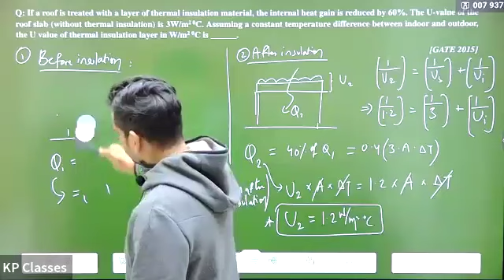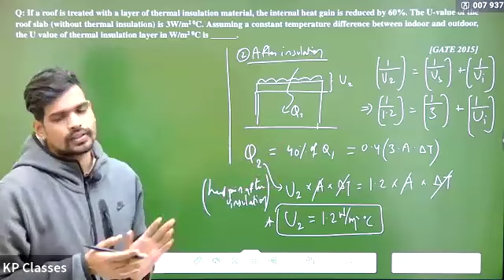Can't we just do Q after is equal to 60% of Q before? Anushka, no, it is reduced by 60%. They're not telling heat gain after treatment is 60% of the original heat gain. They're telling the heat gain is reduced by 60%. So it is not 60% of before. It's like 40% of before, not 60, because it is reduced by 60%. If they had written that the internal heat gain is 60% of the original heat gain, then you will take it as 60% of Q before. It is reduced by 60%, so you will take 40%. I hope that's clear, Anushka.